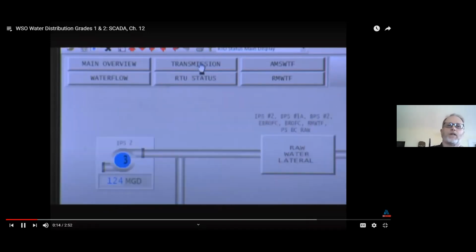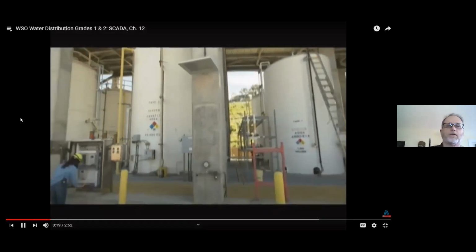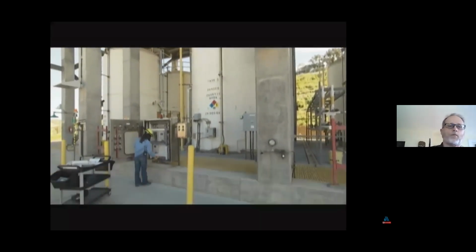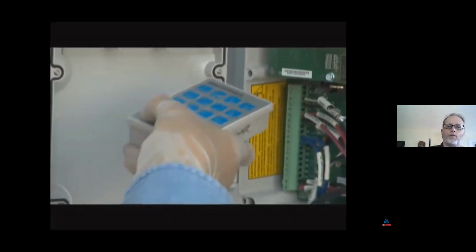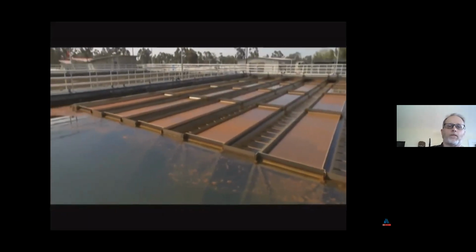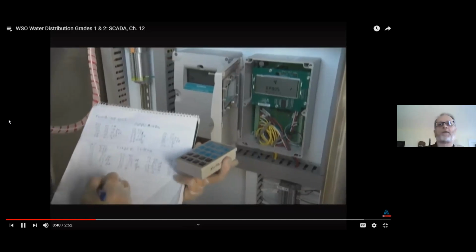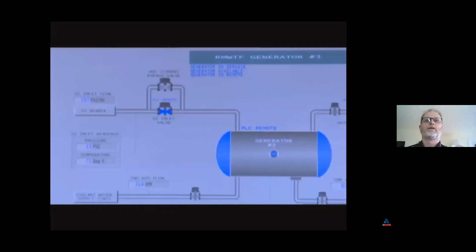Optimized and scaled. For example, a chemical storage tank that is almost empty may generate an alarm. A programmable logic controller at the remote site can operate several automated valves to fill the tank. A well-designed SCADA system can perform many tasks to operate a treatment facility and distribution system. The SCADA system may initiate pre-programmed responses to contingent alarms at remote stations. And while the SCADA can be programmed to react to different events, ultimately, it is the operator who must monitor and use the information being provided by the SCADA system to make important water quality and/or quantity decisions.